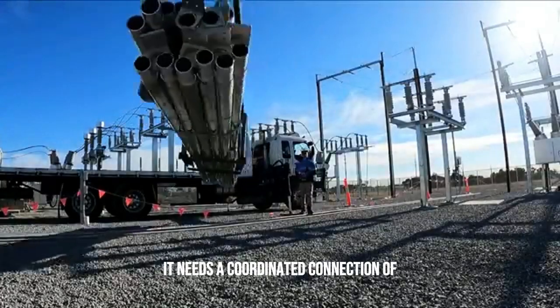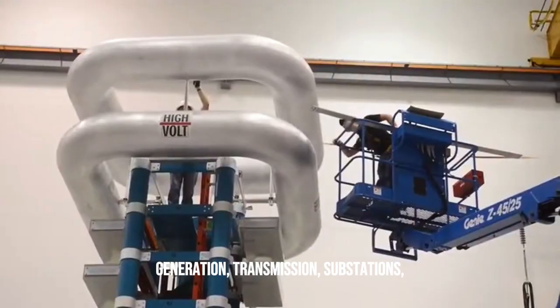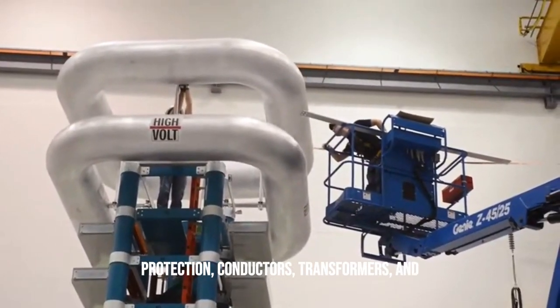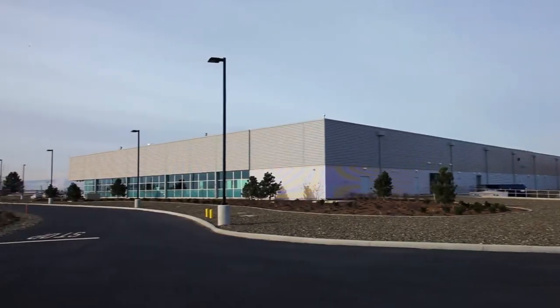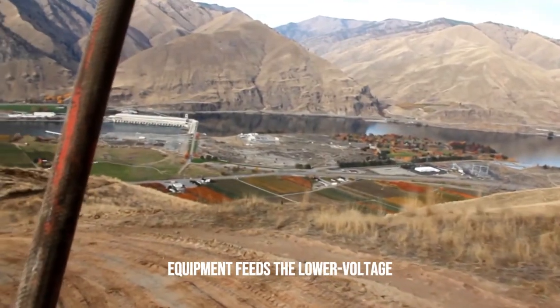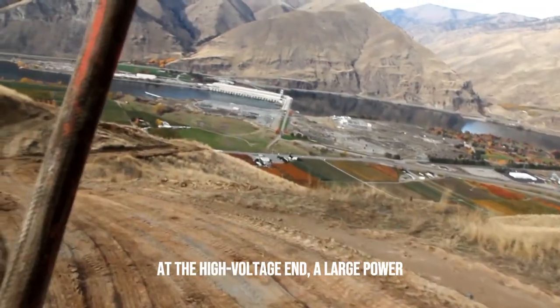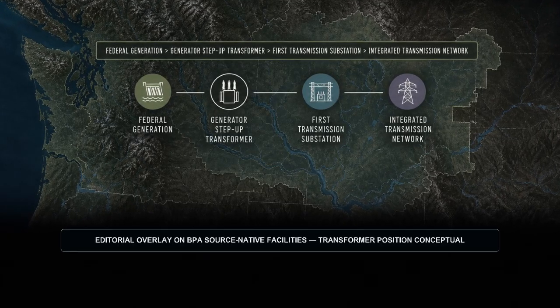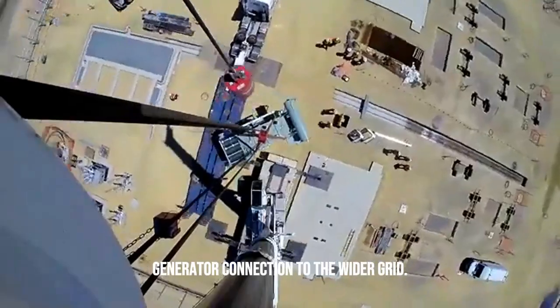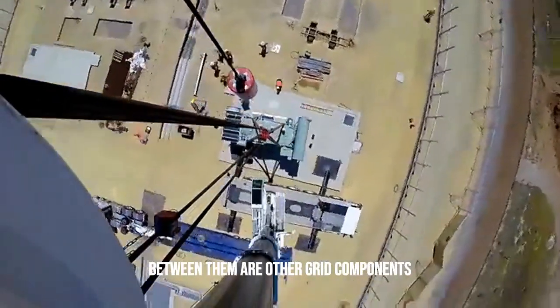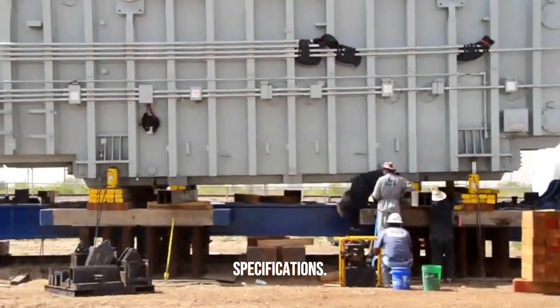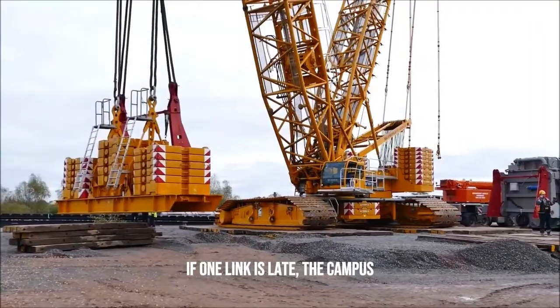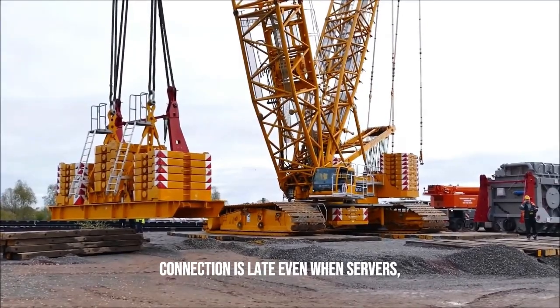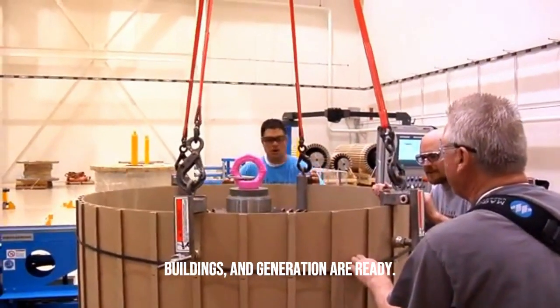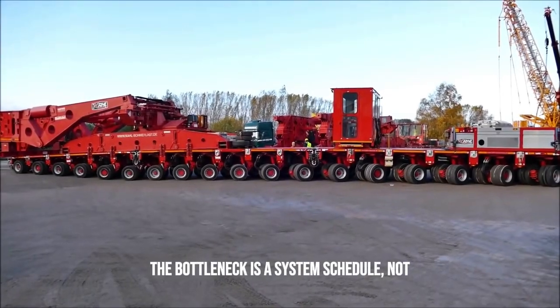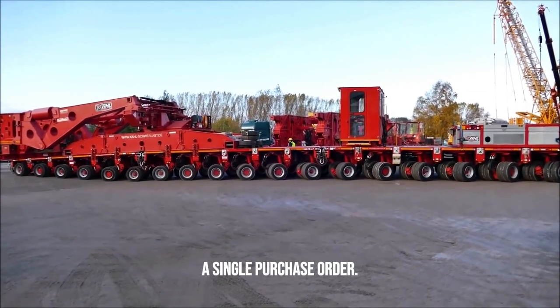It needs a coordinated connection of generation, transmission, substations, protection, conductors, transformers, and local distribution. At the final stages, distribution equipment feeds the lower voltage network. At the high voltage end, a large power transformer is part of the substation or generator connection to the wider grid. Between them are other grid components with different ratings and site specifications. If one link is late, the campus connection is late, even when servers, buildings, and generation are ready. The bottleneck is a system schedule, not a single purchase order.